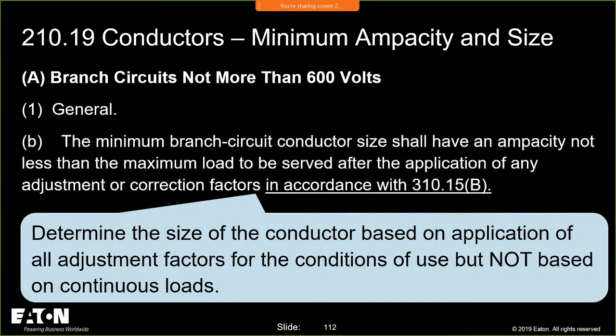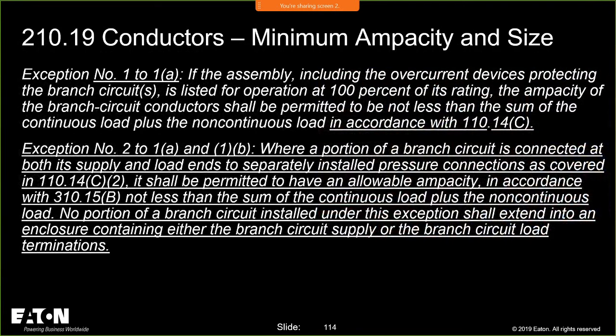Basically, this is just telling you the exact same thing that I just reiterated to you. So you pick the larger of those two, and that is the minimum ampacity and conductor size. And then you pick your overcurrent protective device based upon that conductor. So that was the change that we made in 210.9, and we did the same thing in 210.19.